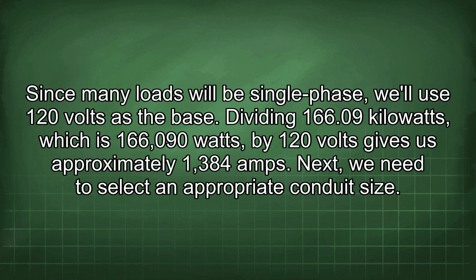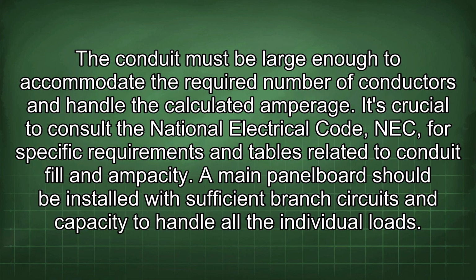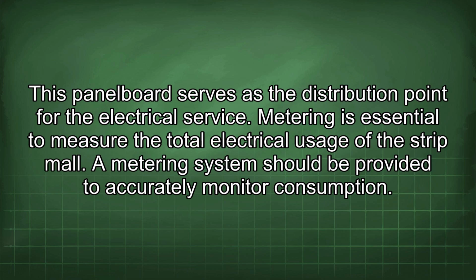Next, we need to select an appropriate conduit size. The conduit must be large enough to accommodate the required number of conductors and handle the calculated amperage. It's crucial to consult the National Electrical Code, NEC, for specific requirements and tables related to conduit fill and ampacity. A main panel board should be installed with sufficient branch circuits and capacity to handle all the individual loads. This panel board serves as the distribution point for the electrical service. Metering is essential to measure the total electrical usage of the strip mall. A metering system should be provided to accurately monitor consumption.